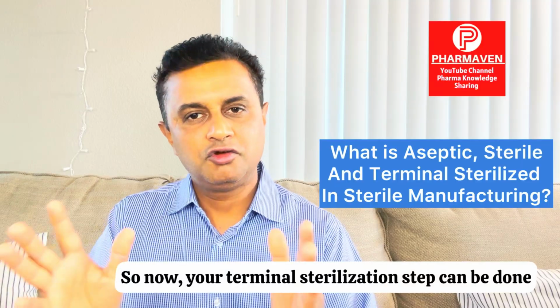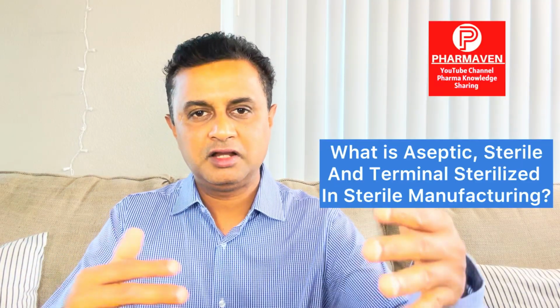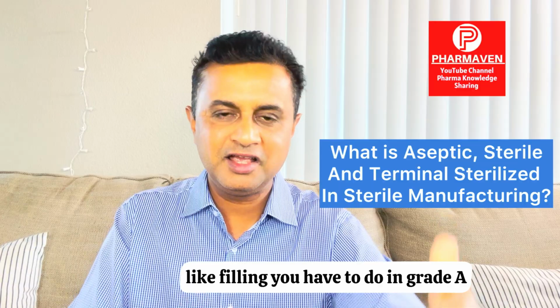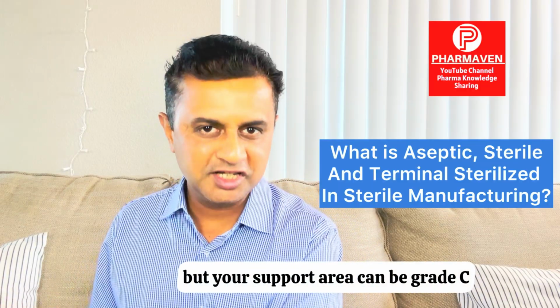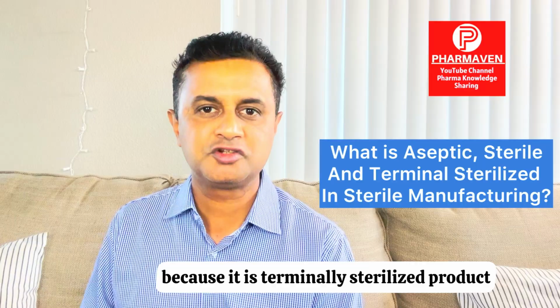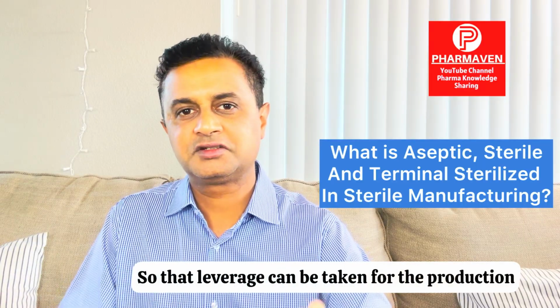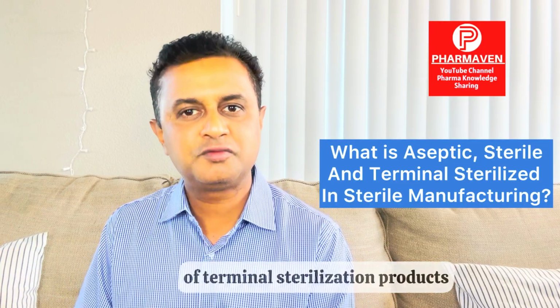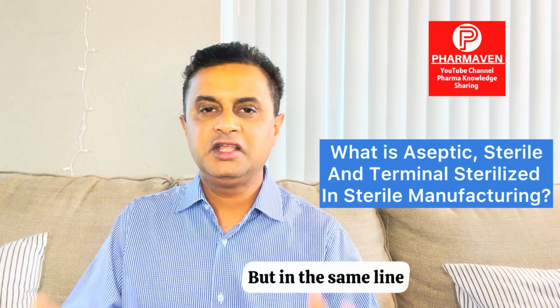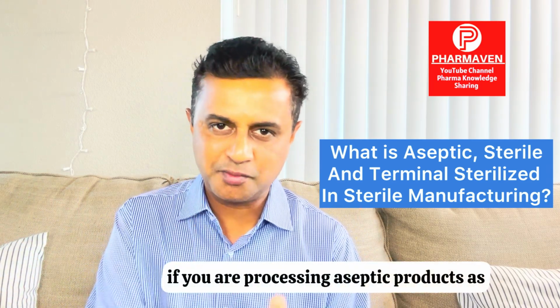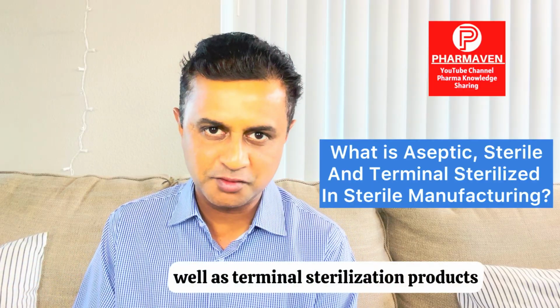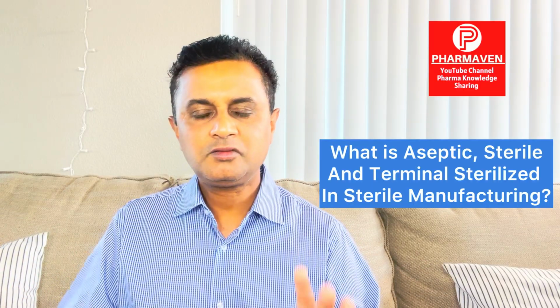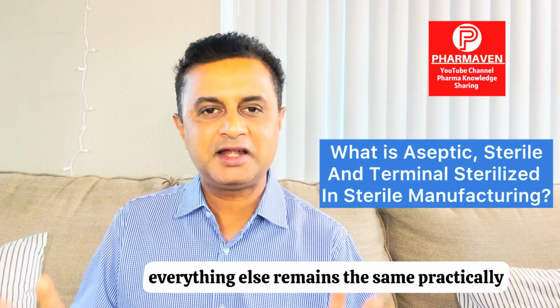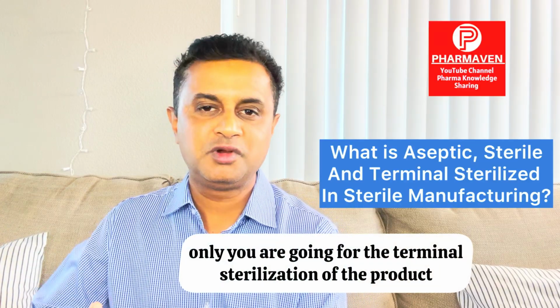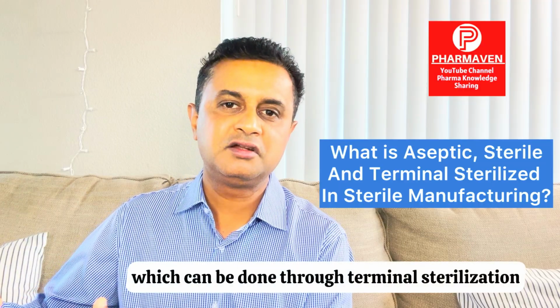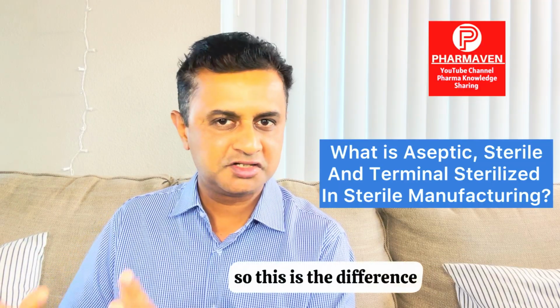So now your terminal sterilization step - filling has to be done in Grade A, but your support area can be Grade C because it is a terminally sterilized product. That leverage can be taken for production of terminal sterilization products. But on the same line, if you are processing aseptic products as well as terminal sterilization products, everything else remains practically the same. Only you are going for terminal sterilization of the product. So this is the difference.